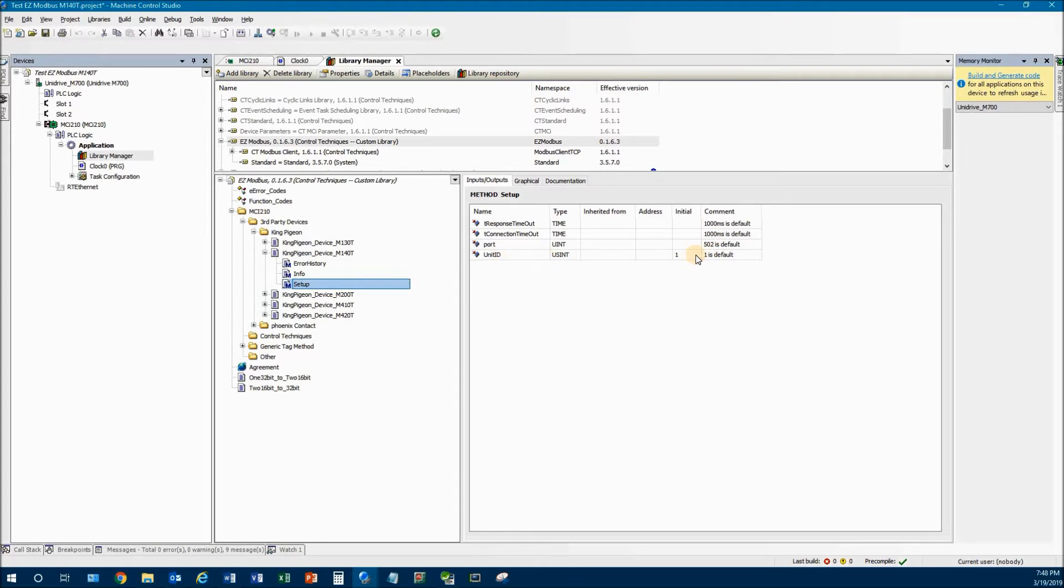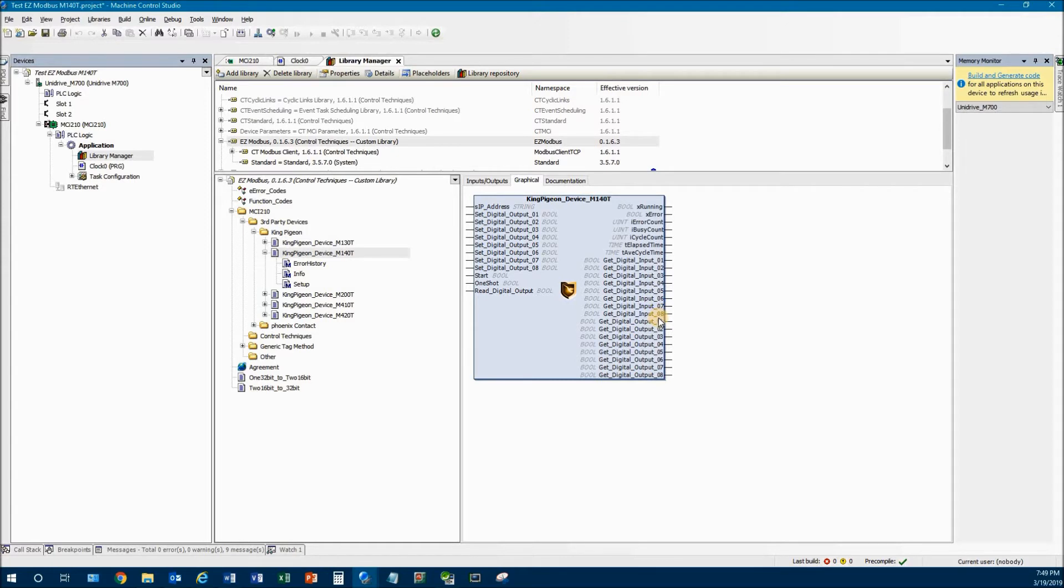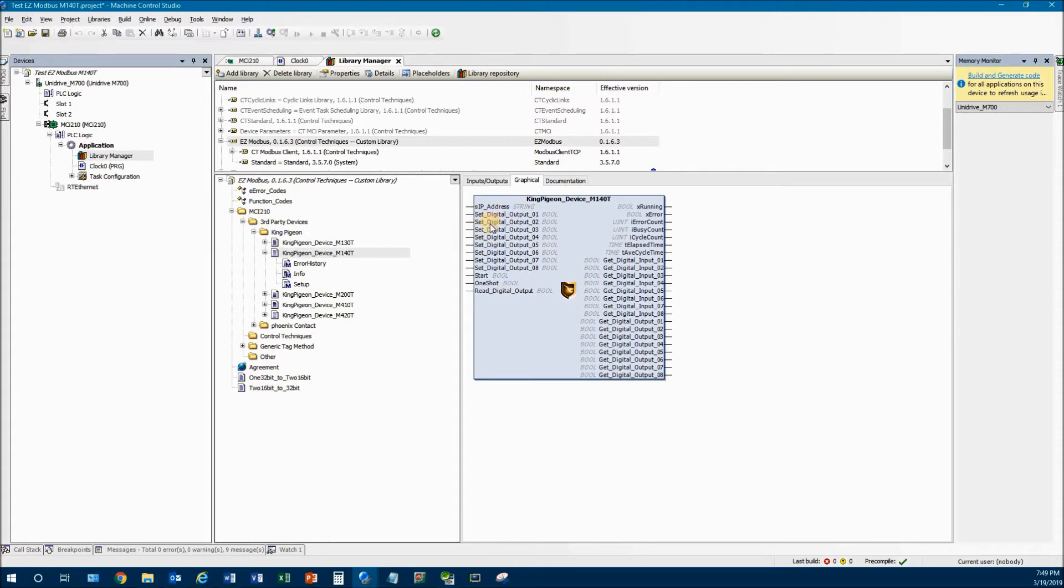So I don't know any reason why you'd really ever change this. If you come to the main part of the block, it shows you what this block looks like. It's got eight digital outputs, eight digital inputs, and then there's another set of eight digital outputs. But technically, these ones are just exactly the same as this. See this input? It says read digital outputs. If this is on, then after it's done writing this, it will go and read the data right back. This is handy for confirming that the data is getting out to the bus coupler, but it also adds an extra step, which slows down the cycle time of your messages.